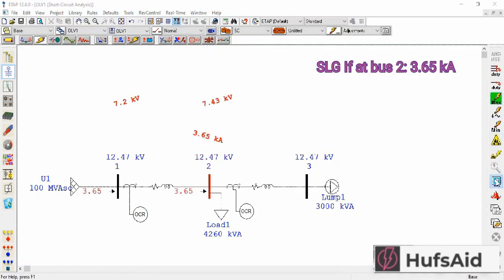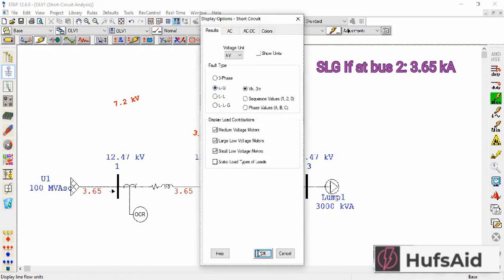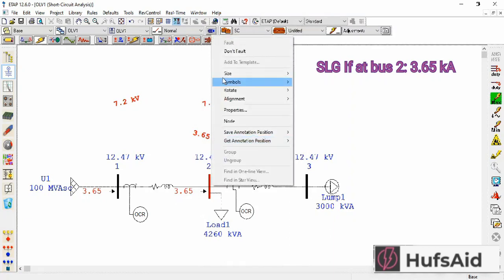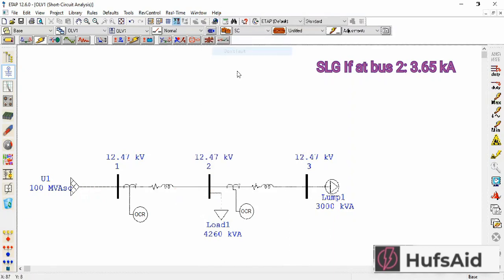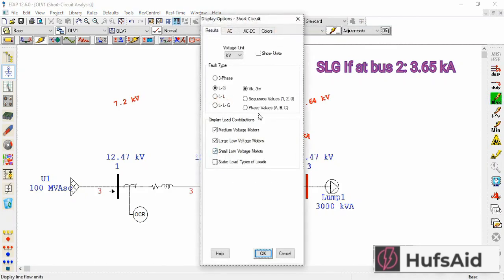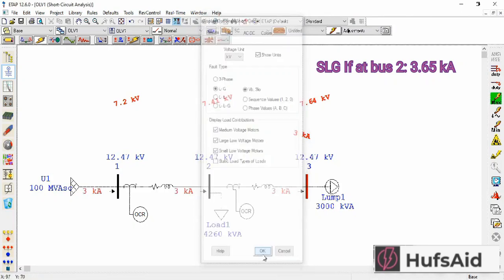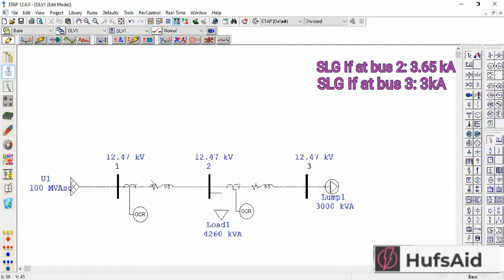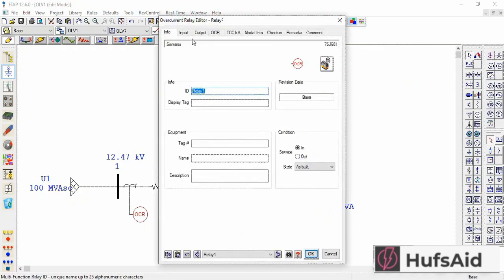I want to know the smallest fault current, so I am going to apply a single line-to-ground fault. If I provide protection against the minimum fault current, my system will be protected for higher values as well. The single line-to-ground fault at Bus 2 was 3.65 kA, and at Bus 3 it is 3.3 kA.